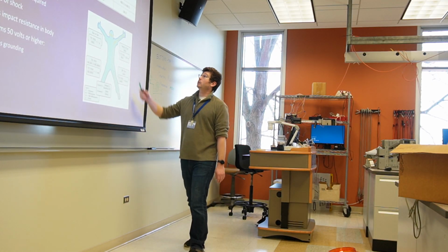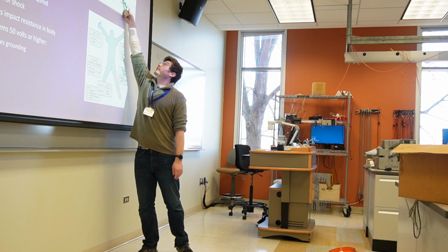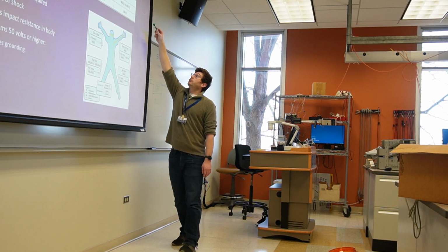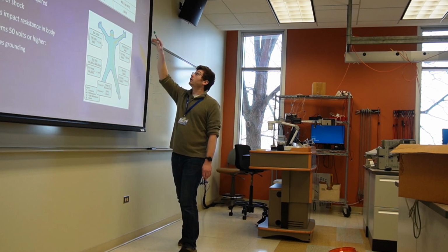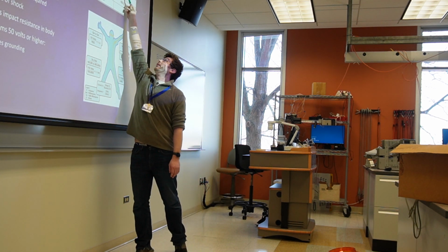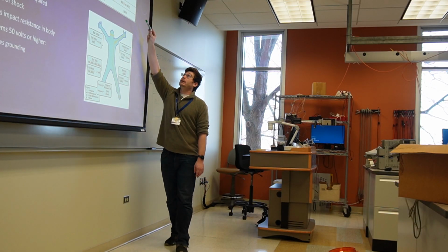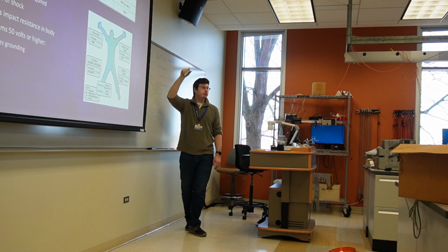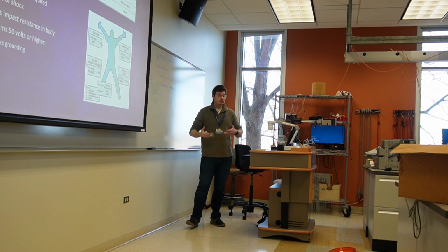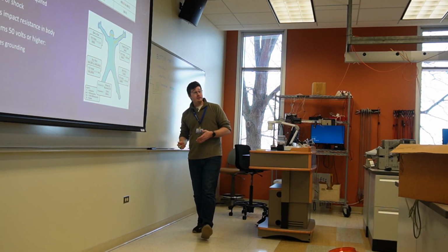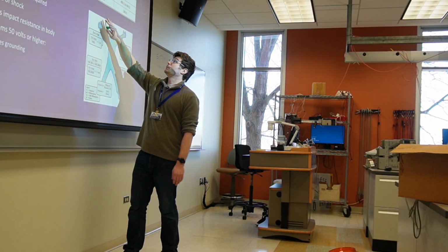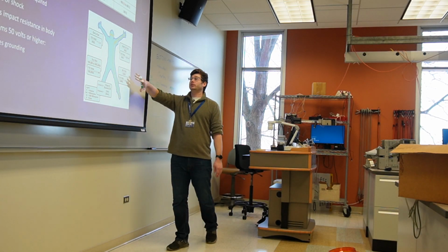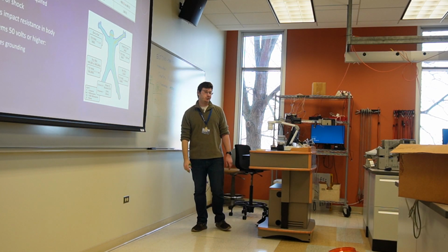If you grab something with a wet hand, that's only 1,000 ohms. So if we're talking 1,000 volts, that's 1 amp flowing through your hand. In the equivalent case, the same situation but with a dry hand, that's 100 times less current flowing through you. It might be the difference between your heart stopping or not, or getting 3rd-degree burns or 1st-degree burns. All this to say, just be aware of yourself and potential means of conducting electricity to and from yourself.